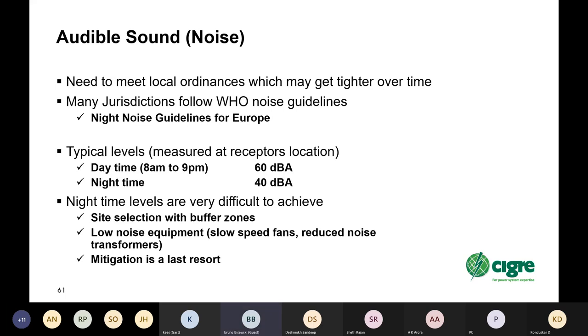So for audible sound, audible sound can be a very large problem. Many jurisdictions follow WHO noise guidelines, and there is a publication for Europe which shows the typical levels are 60 dBA at the receptor location during the daytime. Nighttime can be very much lower at 40 dBA. Those are very difficult to achieve. You need to consider that in your site selection. You need buffer zones to receptor locations, typically people's houses where people are sleeping.